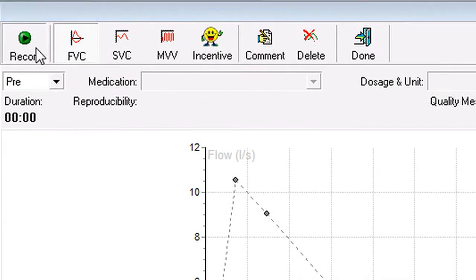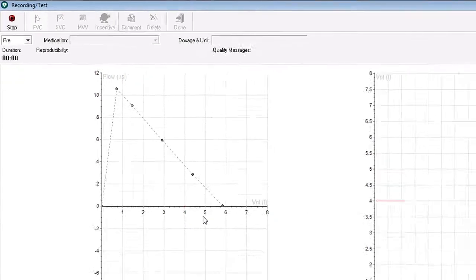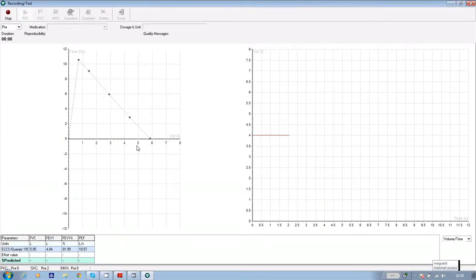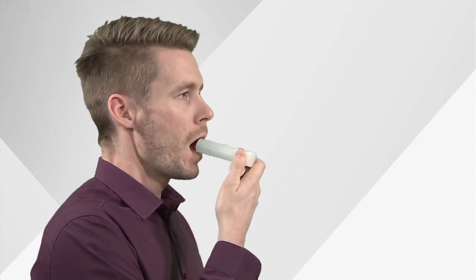Click on record again. Wait for the stabilizing flow sensor message to disappear and then the patient should breathe in as before, place the sensor in their mouth before blowing out as forcefully and for as long as possible before their volume is used up.